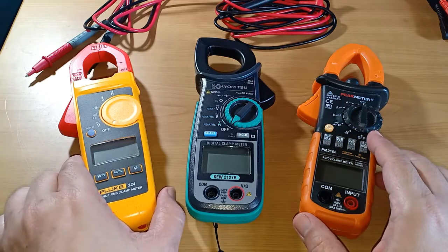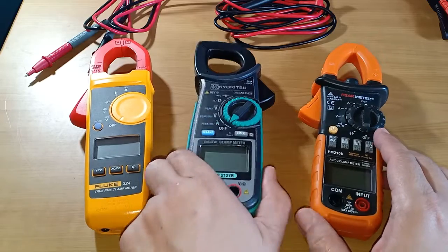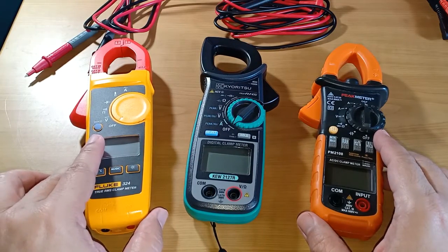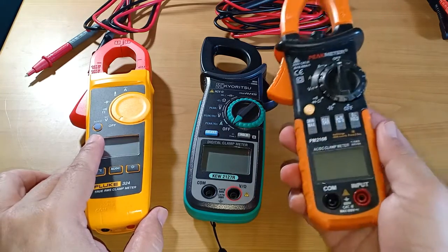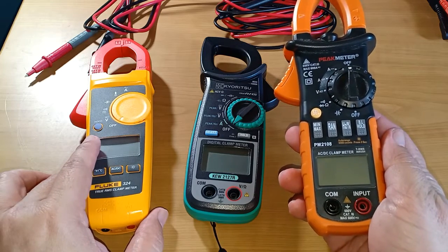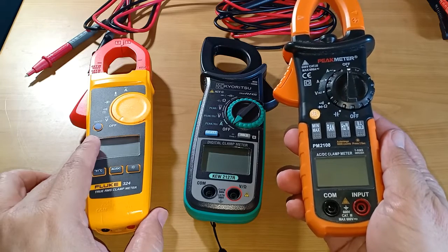I have a Fluke 324 and a Kyoritsu 2127R true RMS clamp meters, but I don't have an Aneng branded unit, so in place of it I will use my Peak Meter 2108 true RMS clamp meter, which in common with an Aning brand clamp meter is also a low-cost alternative.